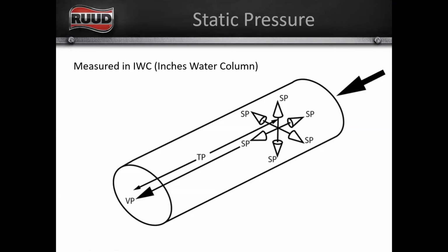So the most common way to measure that airflow is by checking the static pressure, and the static pressure is the pressure that the air moving through the duct applies to the sidewall of that duct. So think about a canvas, a sock duct, or even a balloon, right? The pressure of the air pushing against the sidewall of the duct. The static pressure is what blows up that sock duct, makes it round or cylindrical.